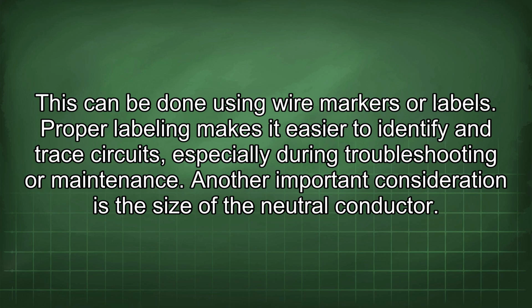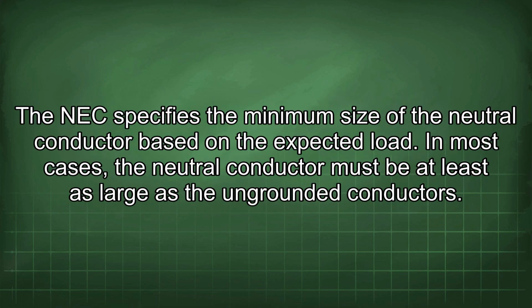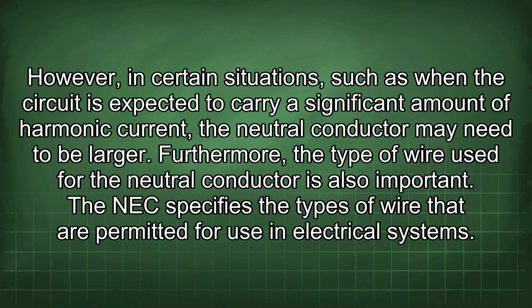Another important consideration is the size of the neutral conductor. The NEC specifies the minimum size of the neutral conductor based on the expected load. In most cases, the neutral conductor must be at least as large as the ungrounded conductors. However, in certain situations, such as when the circuit is expected to carry a significant amount of harmonic current, the neutral conductor may need to be larger.